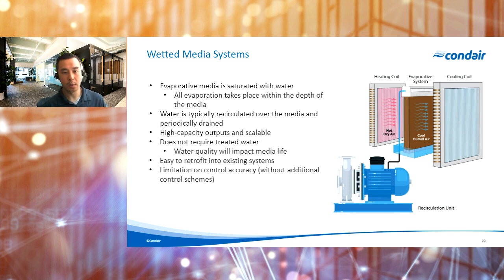Now, in order to reduce the overall water usage with this type of system, any water that is not evaporated typically falls into a sump. In that sump, we typically have a recirculation pump that is used to recirculate and pump water to the top of the media. Now, in terms of where the system is typically installed, we would typically see this between a heating coil and a cooling coil, which allows for any potential preheat that's needed, as well as additional cooling that is potentially needed, or control of the leaving air conditions using that cooling coil that is downstream.